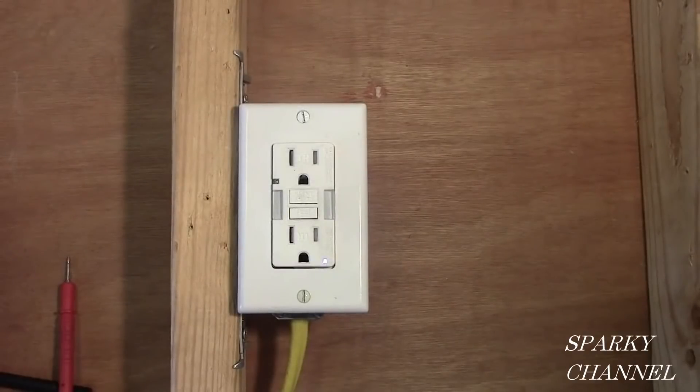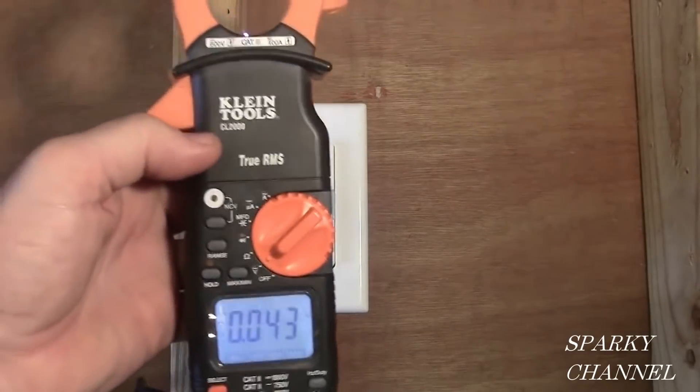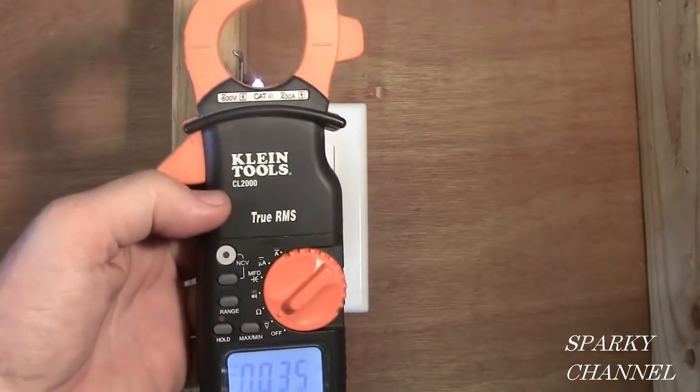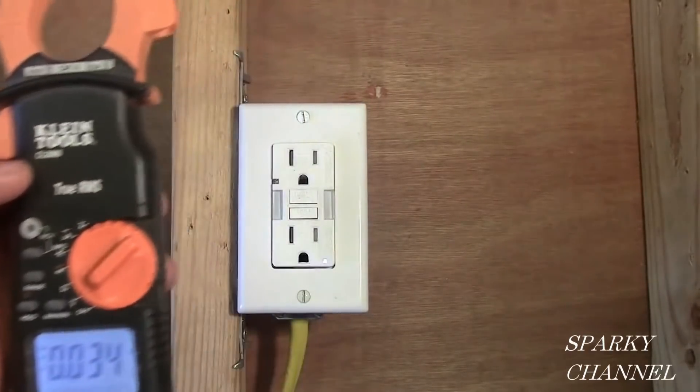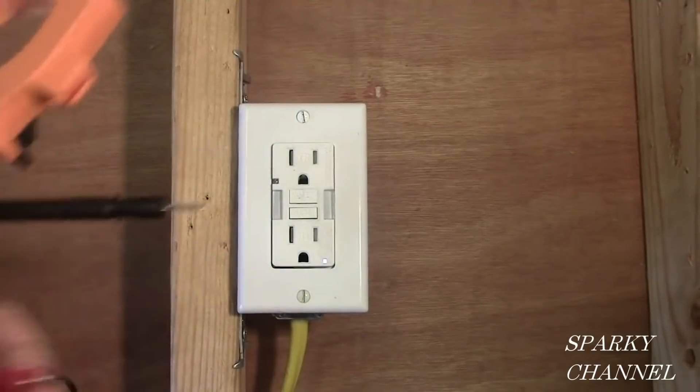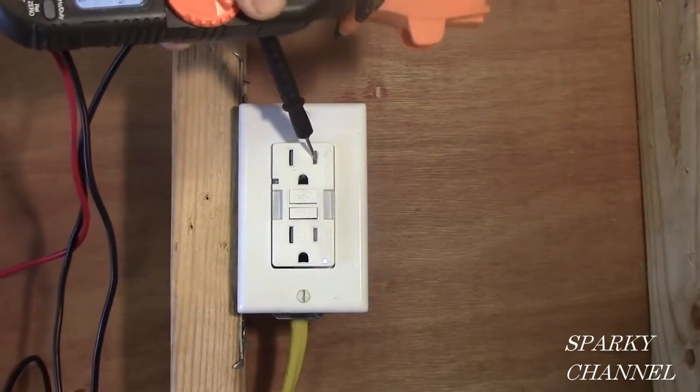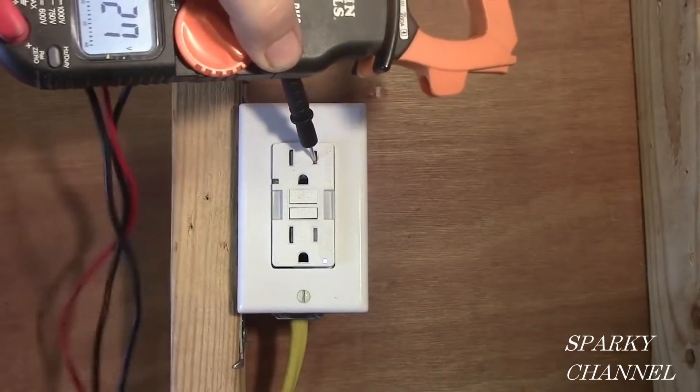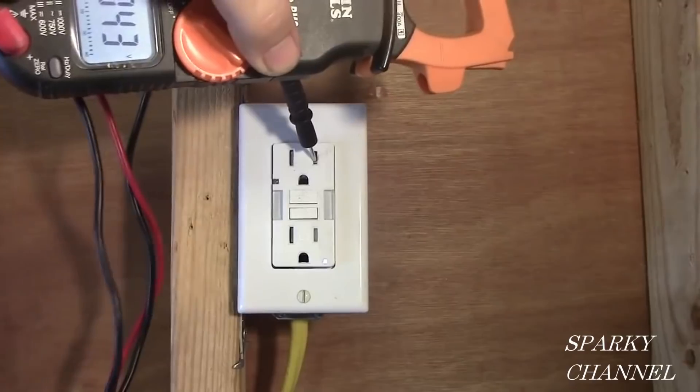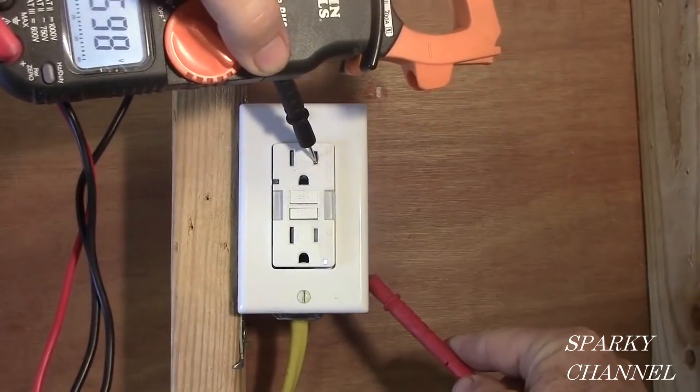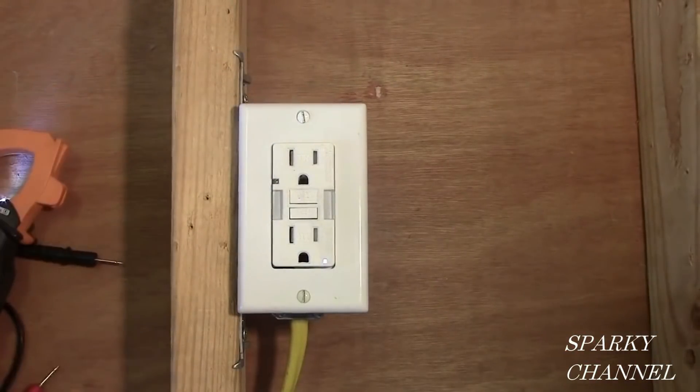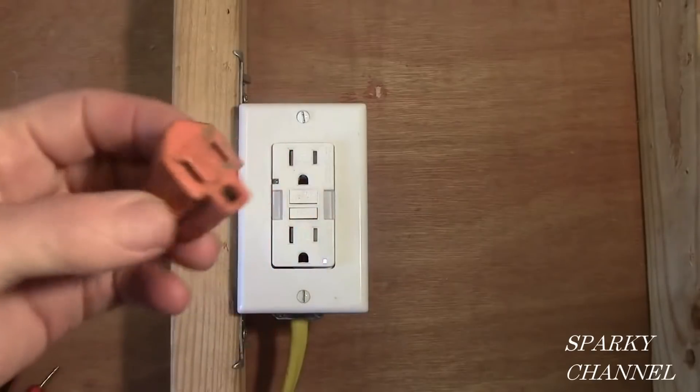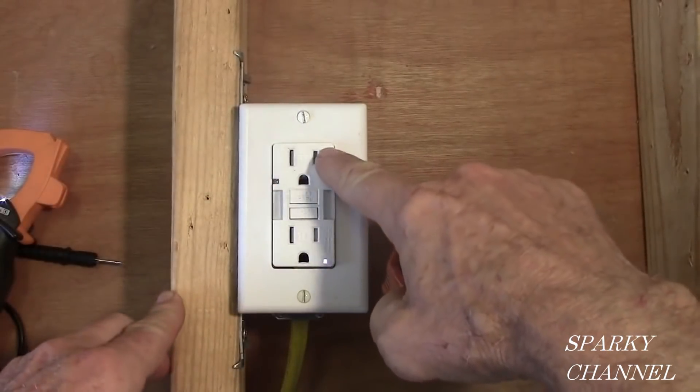For the next test, I'm going to test the bonding of the box itself. Remember, we just used a self-grounding clip to do the bonding. For the test, I'm going to be using my Klein CL2000 True RMS Voltage Meter. Normally you could just put one lead into the hot portion of the receptacle and one on the box, but the problem is this is a tamper-resistant receptacle. So I'm going to use an adapter. Remember, the hot side is right here - it's the short side.